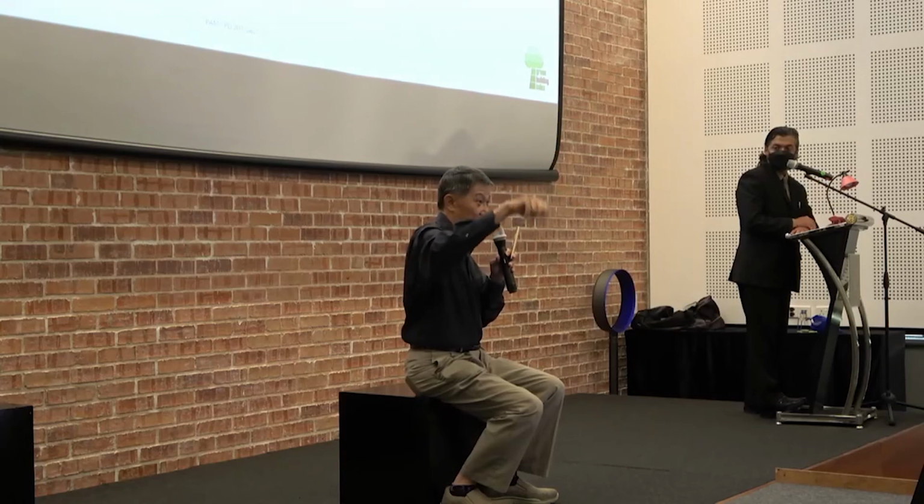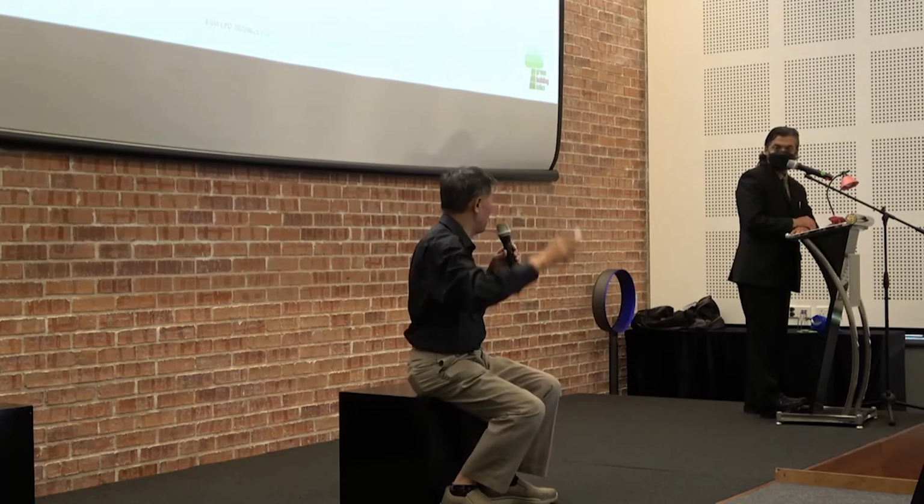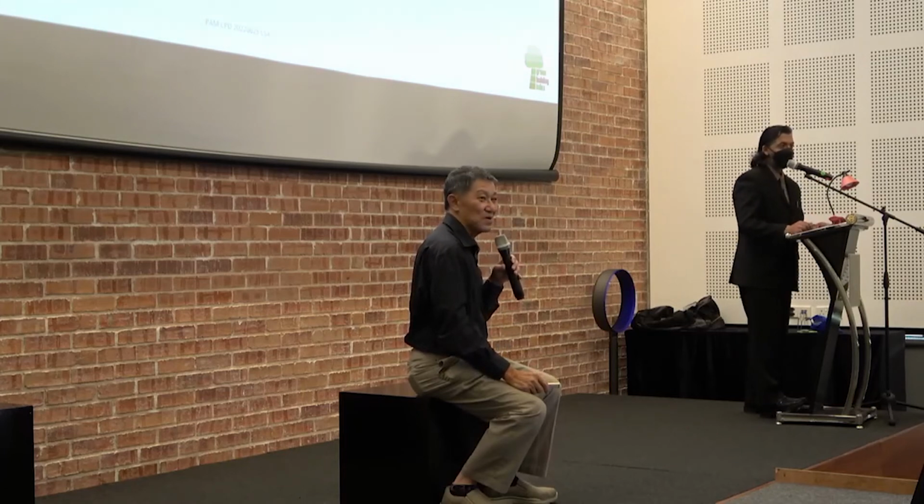Right. And then typically, I notice, not in the KL area, not in the Klang Valley area, but in the outskirts, outside the city center, a lot of the time architects make the mistake of not inspecting before they install the ceiling. So the separation wall between units, they didn't plaster the brickwork. The other is they allow the timber or whatever lightweight trusses to go right through from one unit. It's not allowed under the fire bylaw. So these so-called inspectors go there, open the ceiling, take pictures, then send them to the council. The council will then complain to the board: this guy never followed the bylaw. Ouch. Okay.